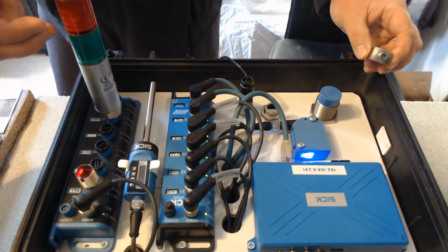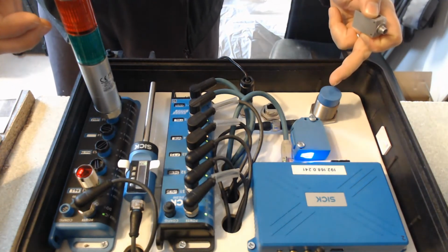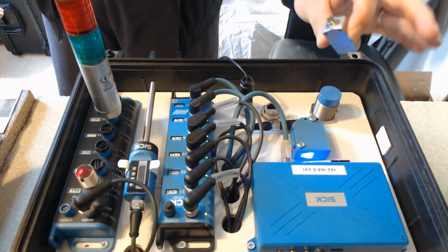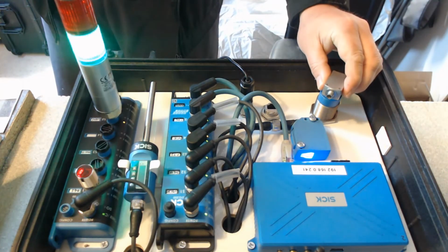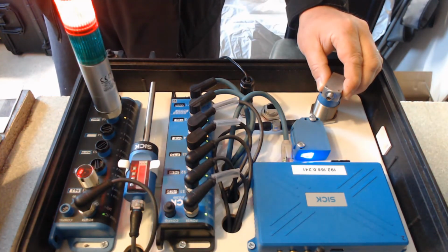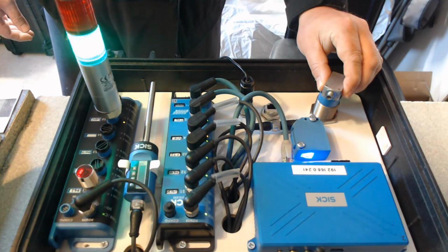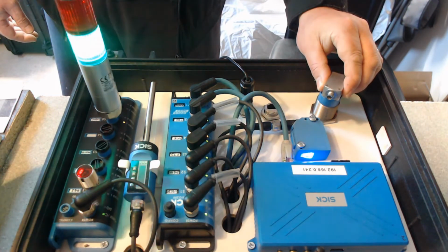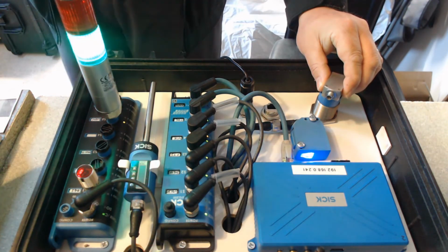The first thing is, using the output lamp and the IMC inductive sensor, we can show the position of the chain. So we're going to use a metal target to pretend to be the chain, and if the chain is in what is perceived to be a good distance from the IMC or the inductive sensor, then we get a green lamp. If the chain drifts, so it's in the wrong position, comes closer to the sensor or further away potentially, then we are outside that range and we get a red lamp. Back in range we get this situation here, and we can see the change there as I move it further and closer to the sensor.